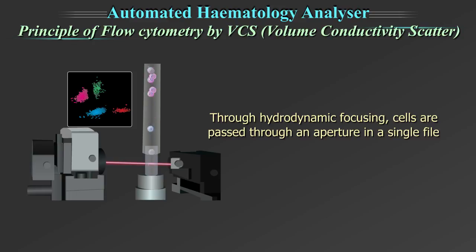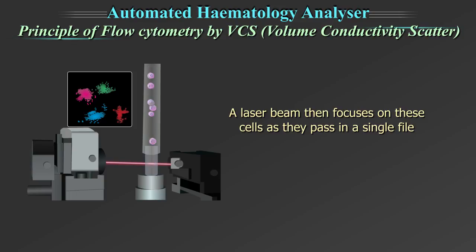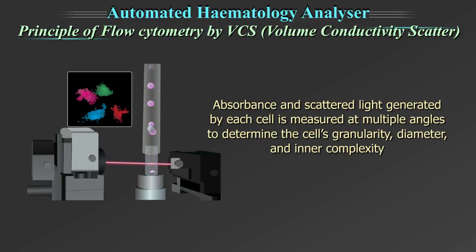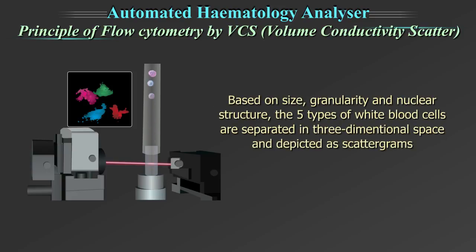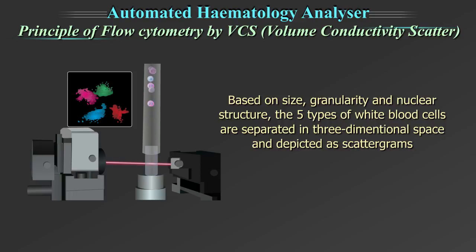Through hydrodynamic focusing, cells are passed through an aperture in a single file. A laser beam then focuses on these cells as they pass in a single file. The absorbance and scattered light generated by each cell is measured at multiple angles to determine the cell's granularity, diameter, and inner complexities. Based on size, granularity, and nuclear structure, the five types of white blood cells are separated in three-dimensional space and depicted as scattergrams.